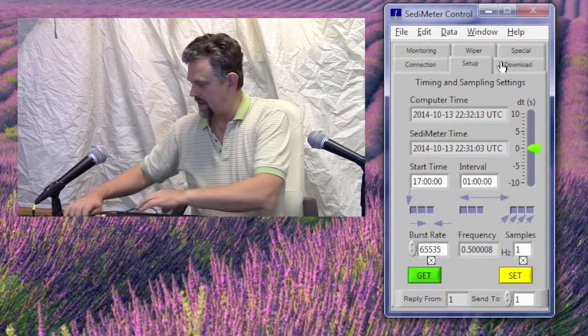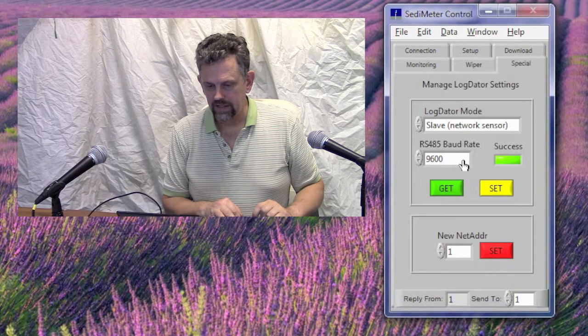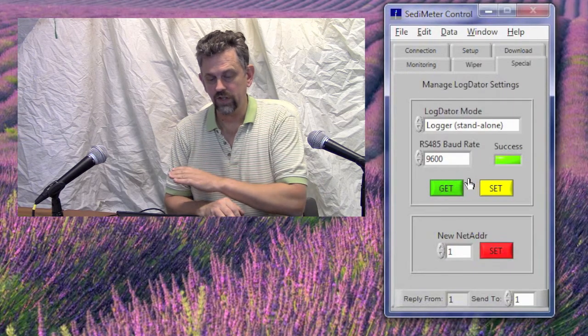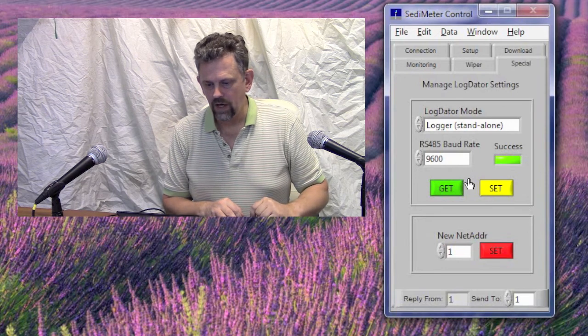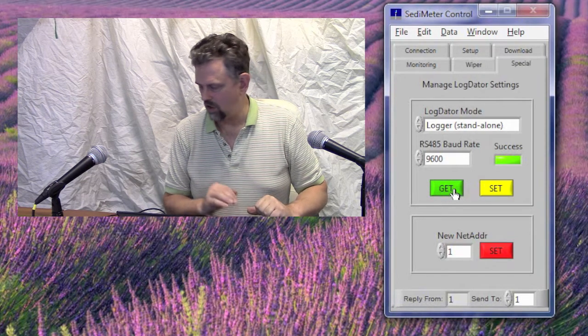Now we have only one thing left to do before we can bring this instrument out to the field, apart from letting the battery charge fully of course. And that is to go to the tab Special, set LogDator mode to Logger. The sedimeter mode is the same here. And click Set. Now it's in Logger mode.